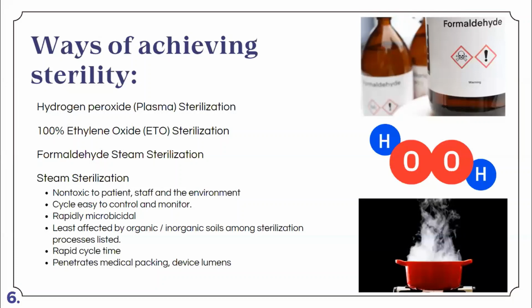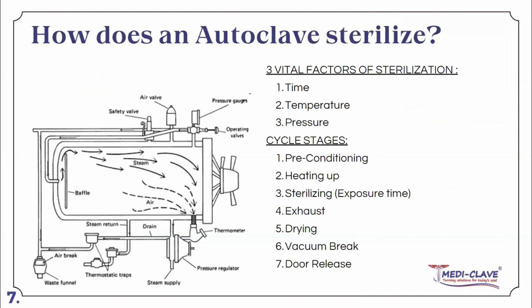So how does an autoclave operate? As you will see on your left, steam enters into the chamber at a set pressure, which in return will determine the temperature required. So pressure and temperature walk hand in hand. This temperature will be maintained for the required time for a specific cycle due to the pressure required and the volume needed in the chamber. So a standard cycle will consist of preconditioning, heating up, sterilizing or your exposure time, exhaust, drying, vacuum break, and your door release, which will enable the autoclave to open its doors.